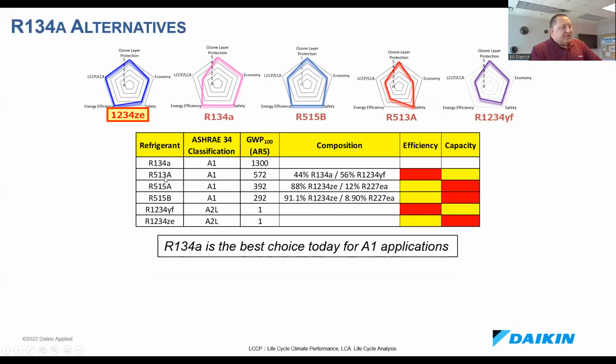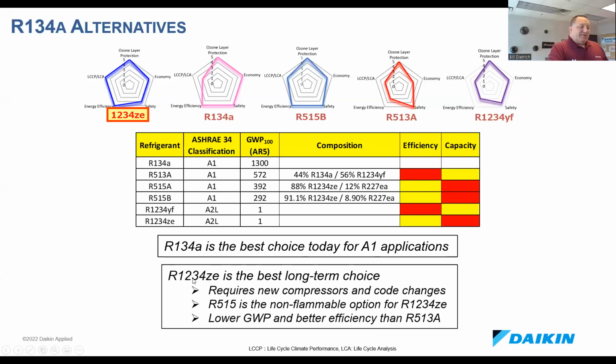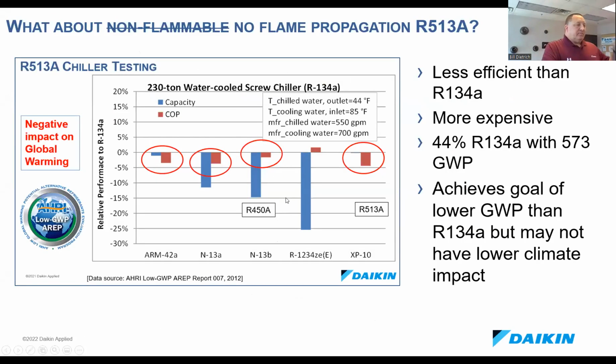But today, we still like our 134A. 513A is becoming available, and you get a bit of a GWP reduction, but you're taking a bit of an efficiency hit too. I'm not sure it's really a good trade-off. And we see 1234ZE being the product that new equipment will be designed around. You'll always have the option with the ZE equipment to put in the 515B if somebody wants the non-flammability, and they just have to take a bit of a compromise on the GWP. This was just some chiller testing done way back in the day on 513A. But in general, you're going to see probably a 3 to 6% efficiency hit when you go from 134A to 513A. So you get a lower GWP, but it may not have a lower impact.